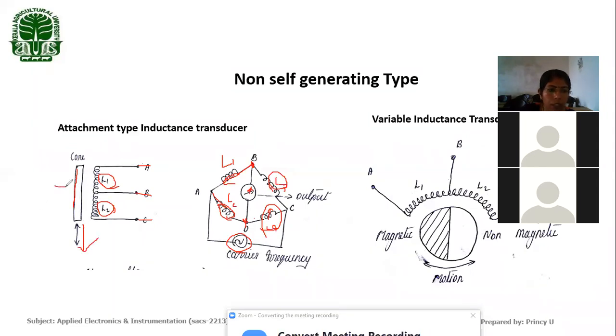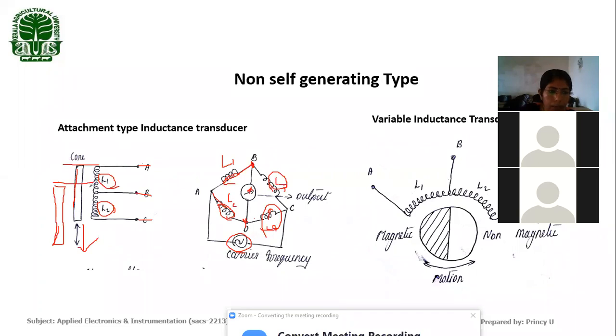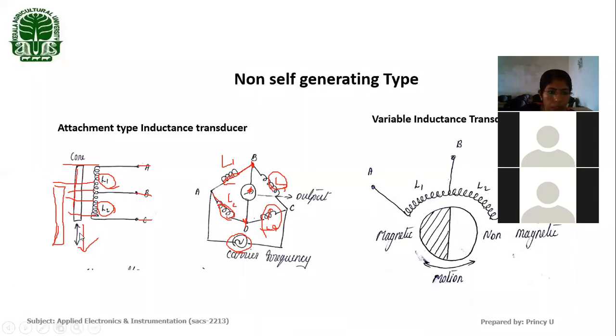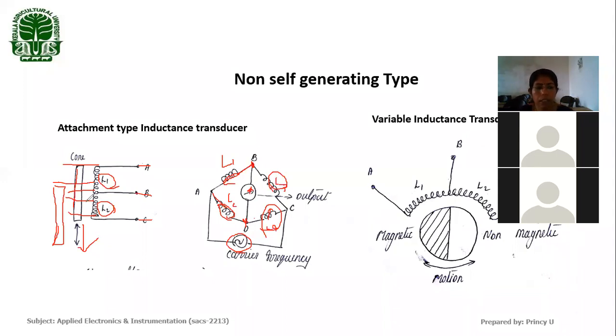When we move this core in the downward direction, the core moves to a new position. At this time, the magnetic reluctance of the area where the core is present decreases. The magnetic reluctance will change across both areas. When we move the core downward, the magnetic reluctance of the first coil reduces while the magnetic reluctance of the second coil increases. This means L1 inductance decreases and L2 increases due to the presence of the high permeability material.